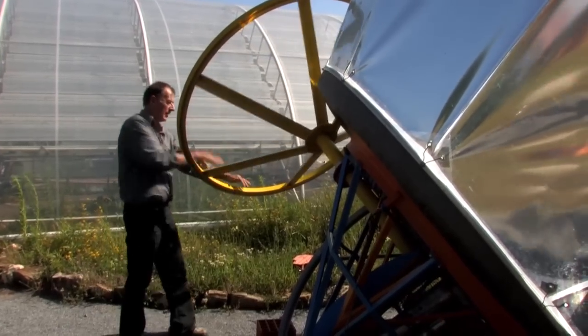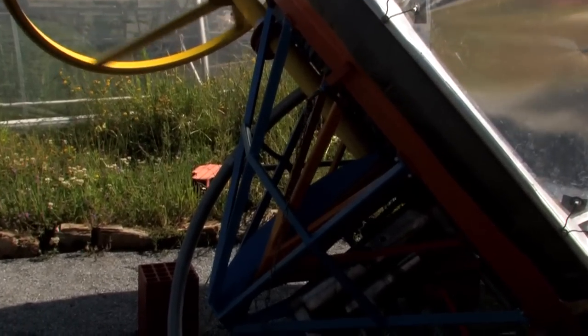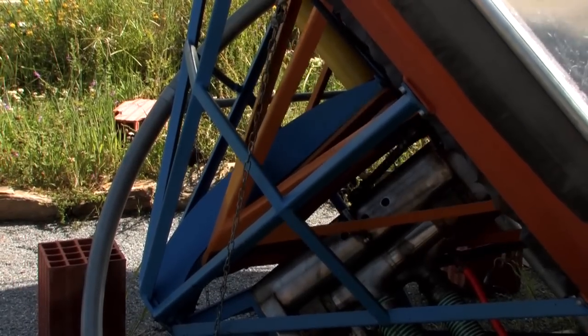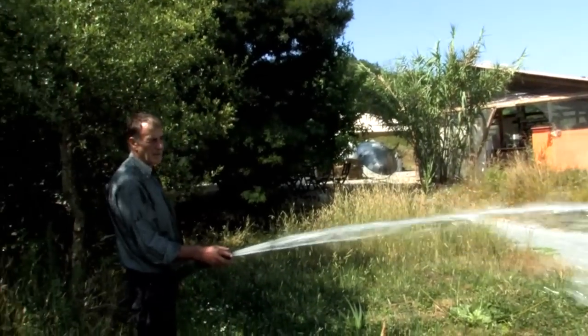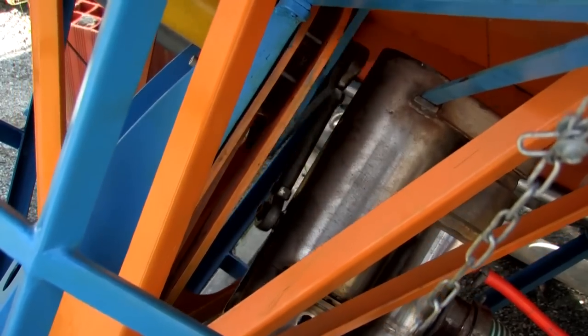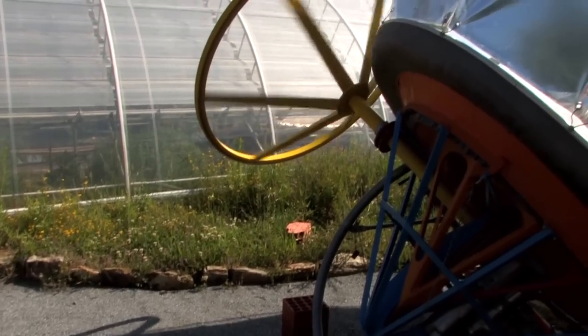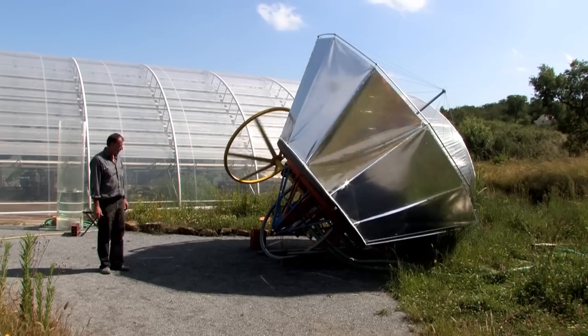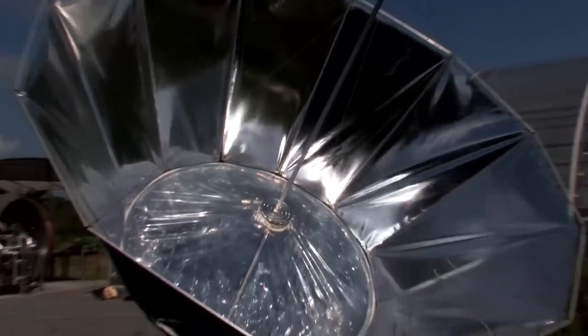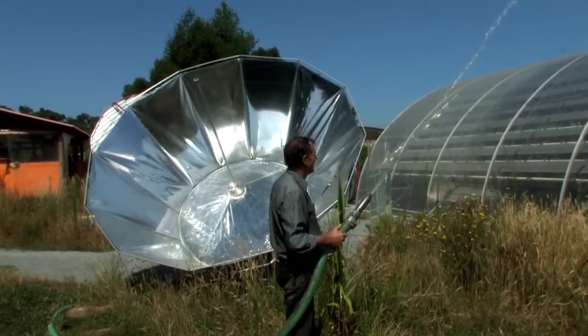Sunvention SunPulse solar-powered water pumps — Sun and water working together. The SunPulse water uses the thermal energy of sunlight directly and efficiently to pump water. The key is world-leading low-temperature Stirling engine technology. A Stirling engine is a heat engine converting heat from any source into mechanical energy. SunPulse engines operate effectively at modest temperatures — around 100 to 200 degrees Celsius — making them simple and reliable to construct and maintain, even under harsh conditions, and ideal for direct stand-alone solar operation. The front face of the SunPulse water is heated by the Sun; cooling is provided by the water being pumped.